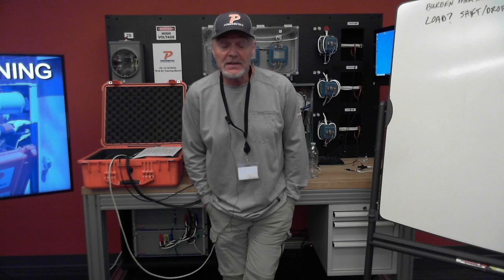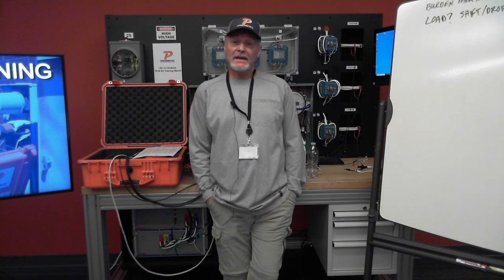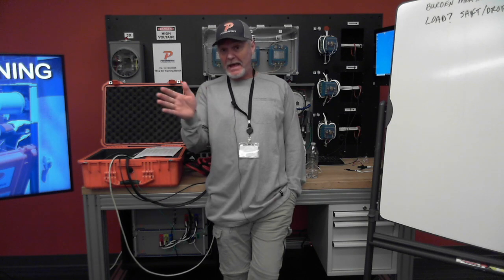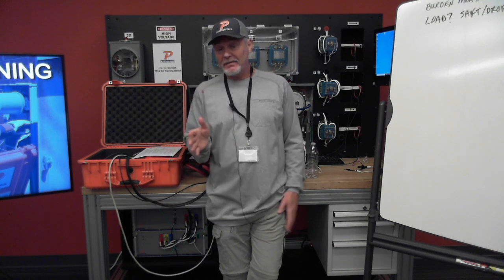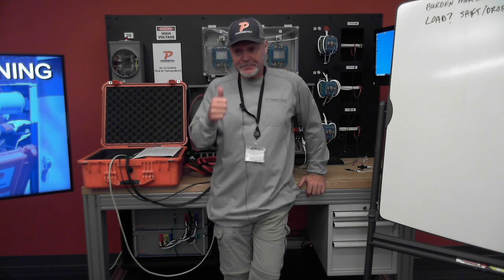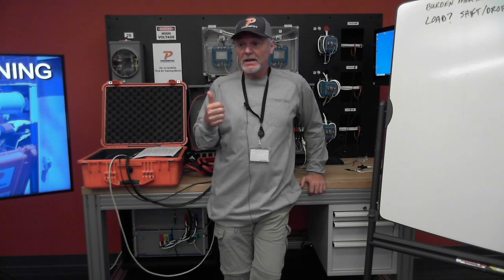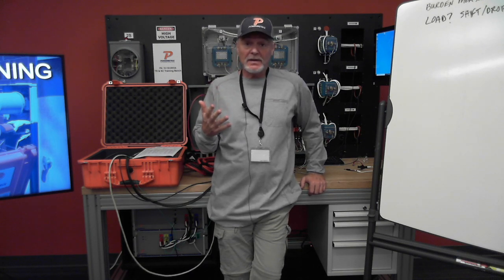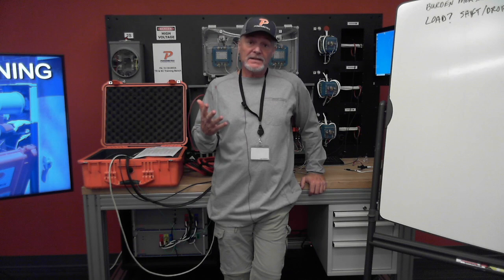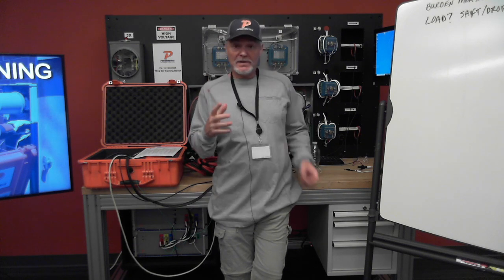We performed the test, and when we looked at the numbers and results, it gave us a path that we followed, and finally we got to the point where on that B phase, that CT just wasn't coming in no matter what we did. It wasn't testing correctly.